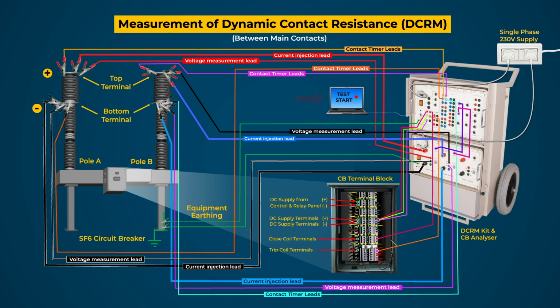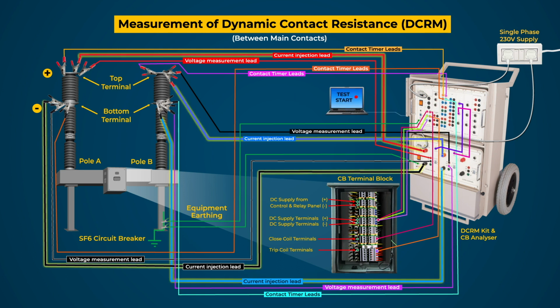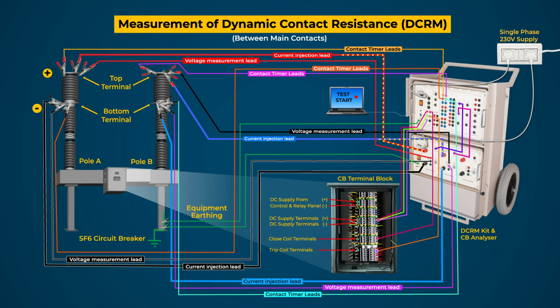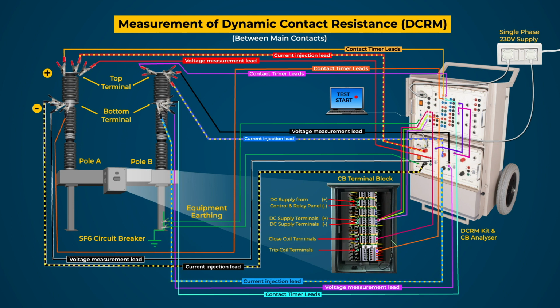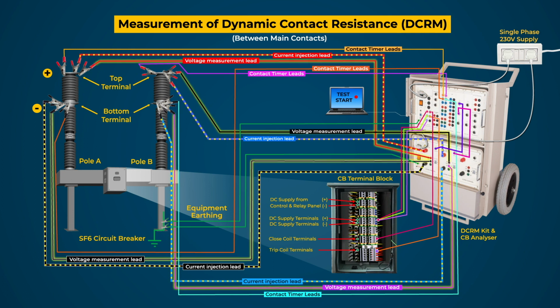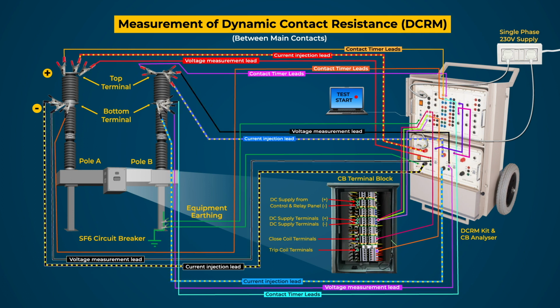Now, press the test button through the laptop connected to the kit. As the test starts, a DC current is injected through the main contacts of the breaker under test. And due to the contact resistance between both contacts, a voltage drop is observed between them.